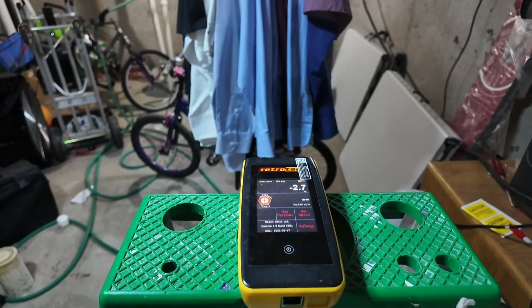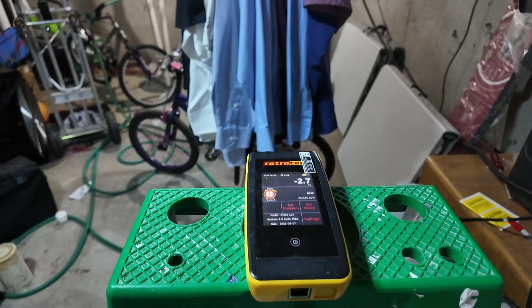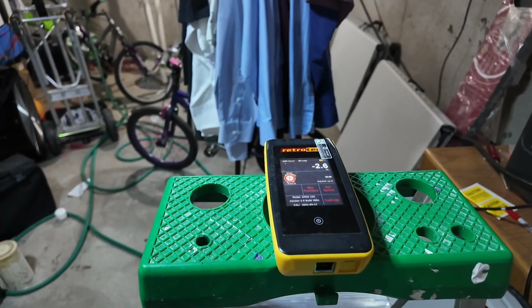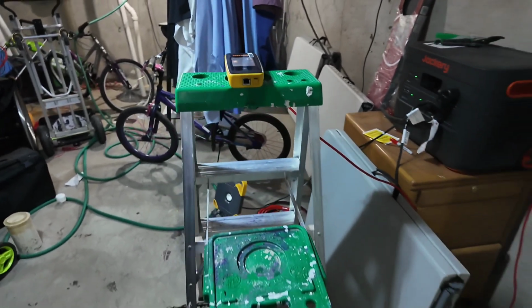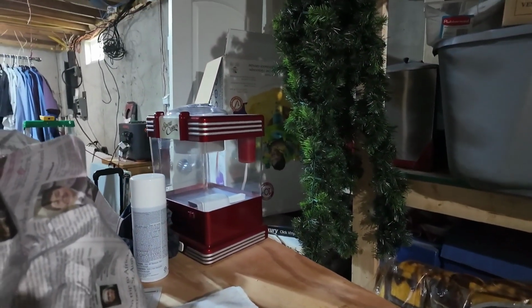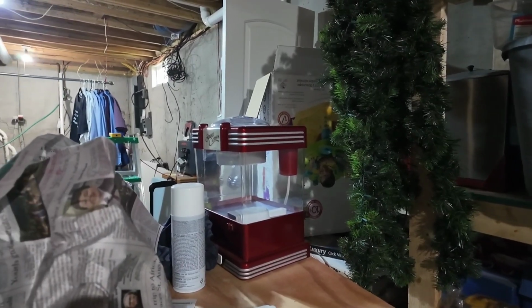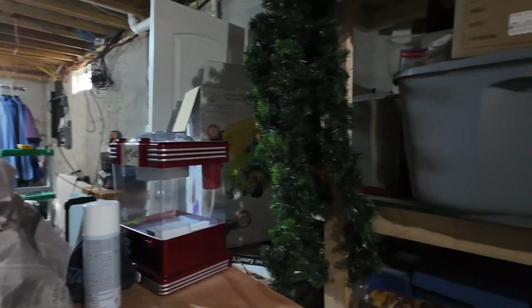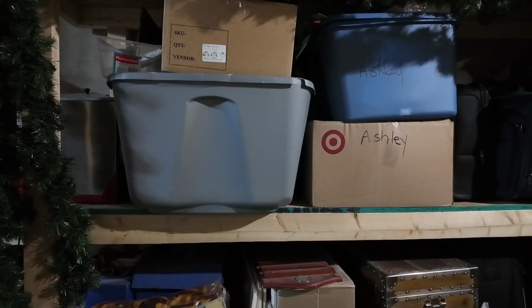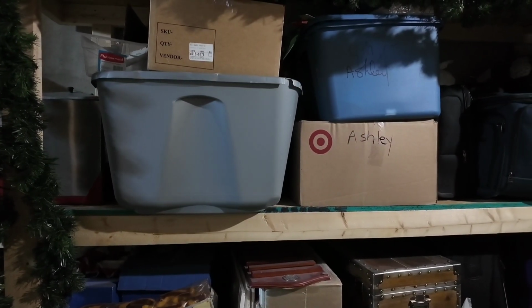And it looks like it made it more negative because it went from a negative 2.4 to negative 2.8. So we would then leave it on according to our guide. It says if the pressure in the CAS becomes more negative with reference to outdoors after the blower is turned on, leave the blower on during the combustion safety test. We did. Now, or it did, and we will.